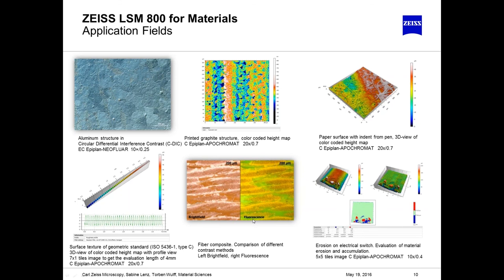One main application is to determine surface roughness. Surface roughness standards are available on the market, and according to norms, a specific evaluation length of four millimeters is needed. Since four millimeters is larger than one single microscope image field of view, by stitching different tile images together we can reach the required evaluation length with the confocal microscope. Fluorescence contrast can also reveal additional information, and an extensive set of evaluations are available with our software ConfoMap.